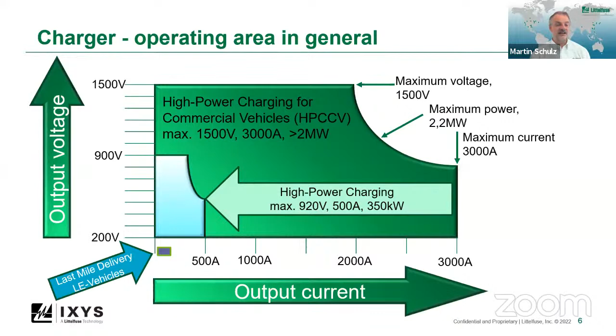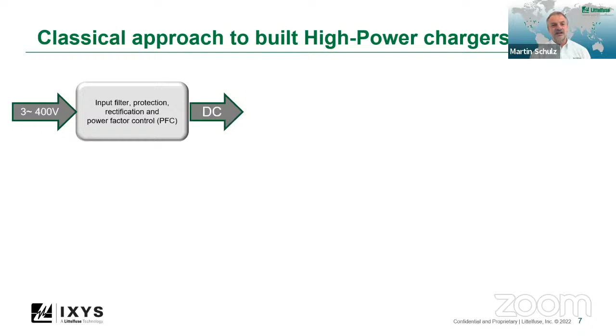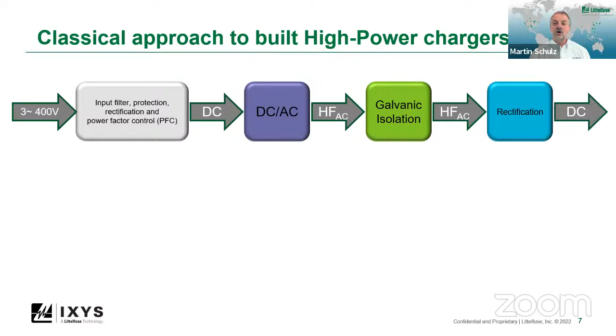There is something that you can consider a classical approach to build those high power chargers. You have a three-phase supply, typically 400 volt, which is given to an input stage for rectification. In this power regime, typically power factor correction is a must-have. And you get a DC voltage that is then again transferred into a high frequency AC. This high frequency AC is used to drive a galvanic isolation, so typically a transformer in LLC configuration. And you get a high frequency output from it, which needs rectification to support the DC voltage of the battery.